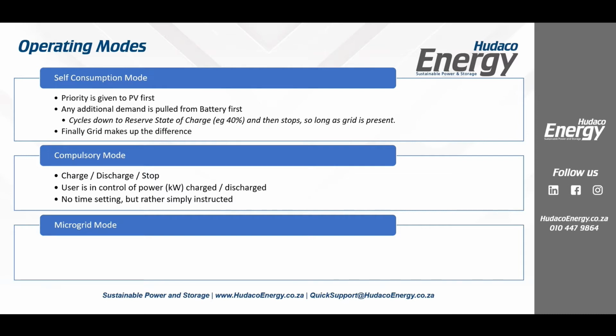Also, in compulsory mode discharge, if your loads are only, let's say, 300 watts at home and you've told it to discharge 2 kilowatts, it is going to discharge the rest to grid, just to be aware. It can discharge back through your grid port if you need it to. Very important, please remember, there's no time setting on this. You can't say, I want you to charge just for 1 hour under compulsory mode. There's a separate setting called forced charge where we can do timing windows, and we'll discuss that a little later. But compulsory mode is basically like a manual switch where you can say in, out, or stop.